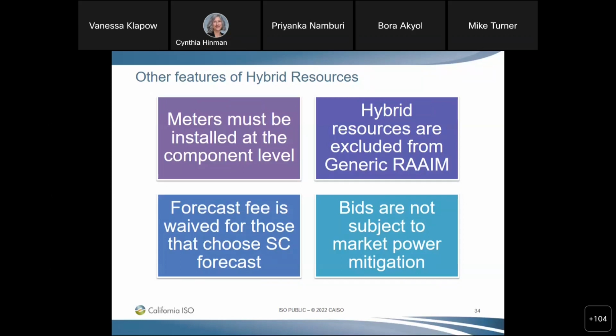Pat McCarthy with AES shares the same concern as Bora. Using the 233 megawatt example from the presentation, even a 5 MVA inverter, larger than what's available, with only 2 inputs to the low side, would be about 1 DC meter per 2.5 megawatts, not counting substation feeder metering needed to further disaggregate per resource from the point of interconnection. This means hundreds of meters, representing whole percentage points of project cost, and clarification is wanted before committing to that kind of metering.